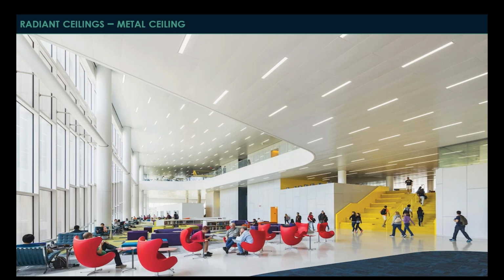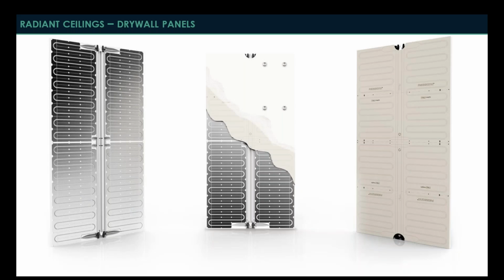Now, these metal ceilings are not 100% active radiant ceilings. It may be portions of the ceiling system are active and portions are inactive, but the real benefit of the metal ceiling system is that it creates a very homogeneous ceiling look. You can't tell what portion is active and what portion is inactive. It all sort of looks the same and has a very, very clean look in that regard.